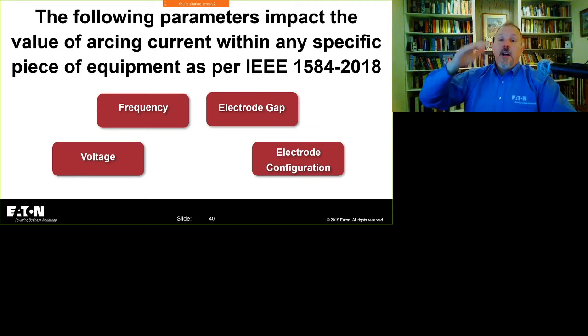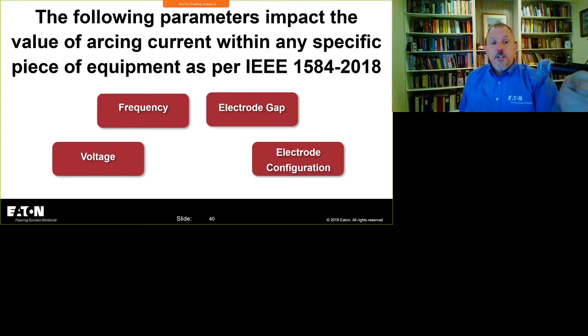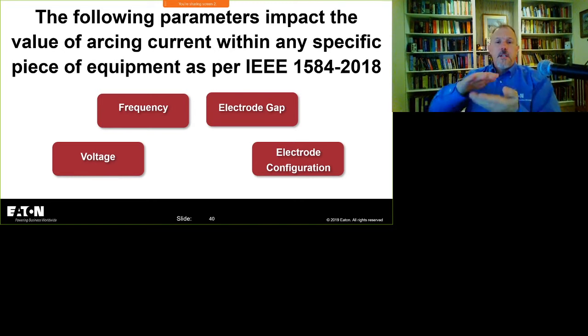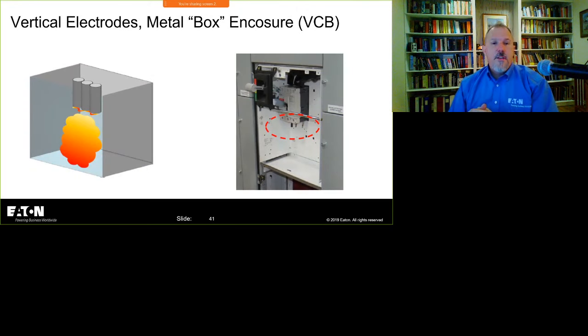Frequency is obvious. IEEE 1584, the limits are 50, 60 hertz. Obviously, voltage, we already talked about the pressure. The electrode gap, we talked about that as well. And that's the distance between the conductors, the buses, and things like that. And every piece of equipment may be a little different. And then you have the electrode configuration. We're going to talk about the electrode configuration because that's new in 1584.